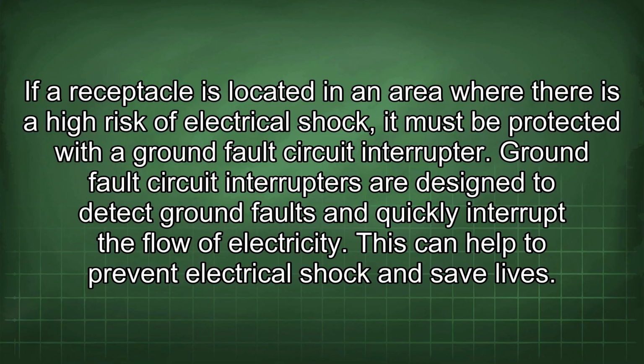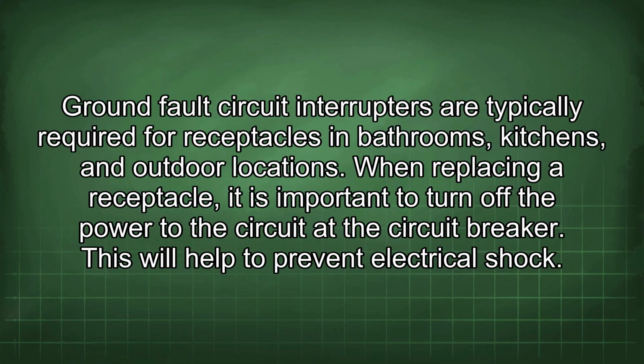If a receptacle is located in an area where there is a high risk of electrical shock, it must be protected with a ground fault circuit interrupter. Ground fault circuit interrupters are designed to detect ground faults and quickly interrupt the flow of electricity. This can help to prevent electrical shock and save lives. Ground fault circuit interrupters are typically required for receptacles in bathrooms, kitchens, and outdoor locations. When replacing a receptacle, it is important to turn off the power to the circuit at the circuit breaker. This will help to prevent electrical shock.